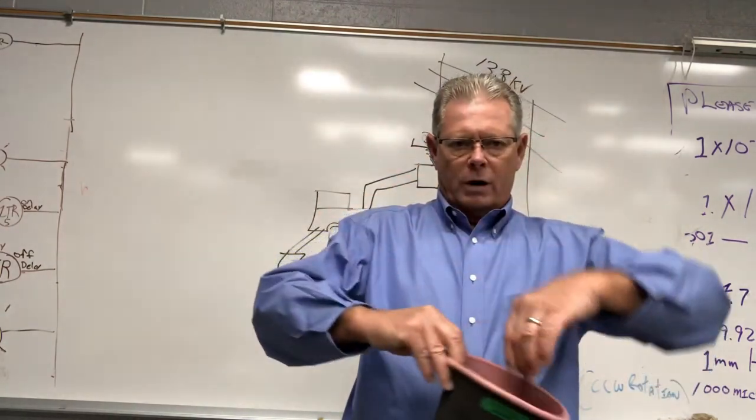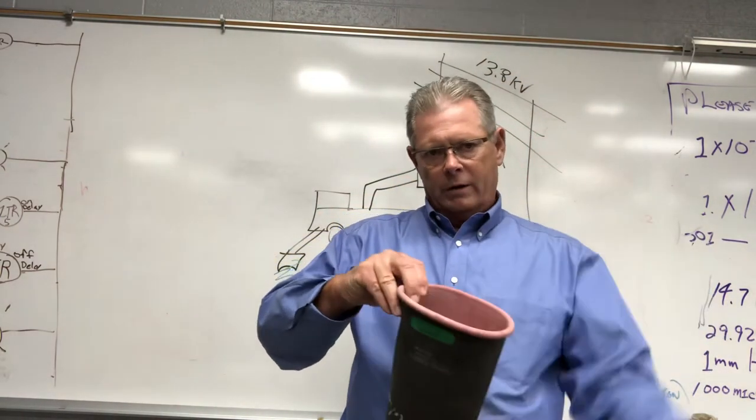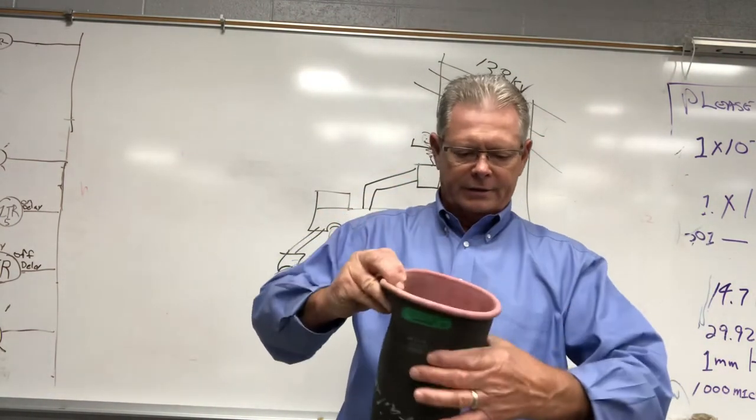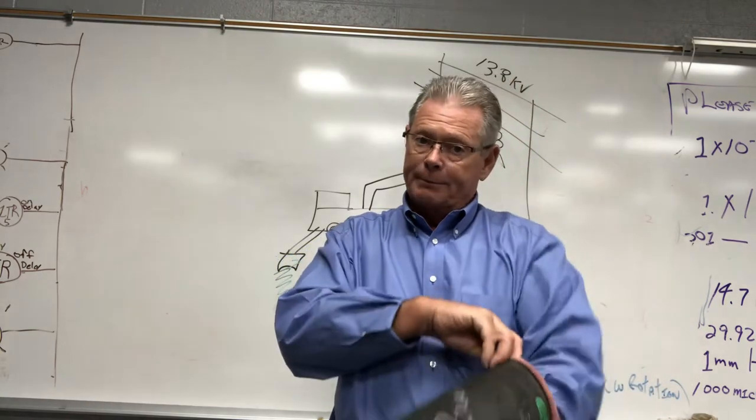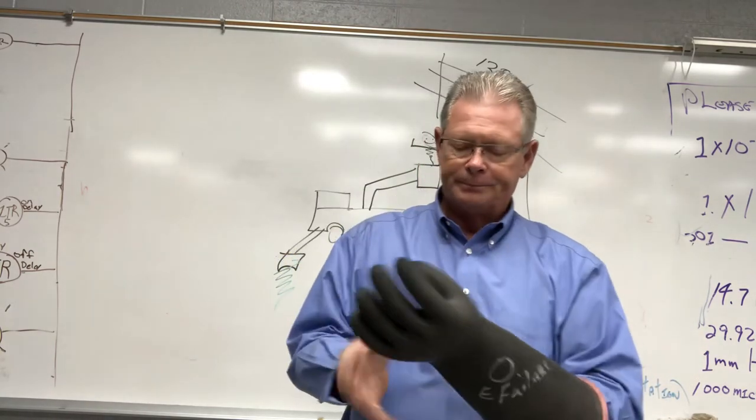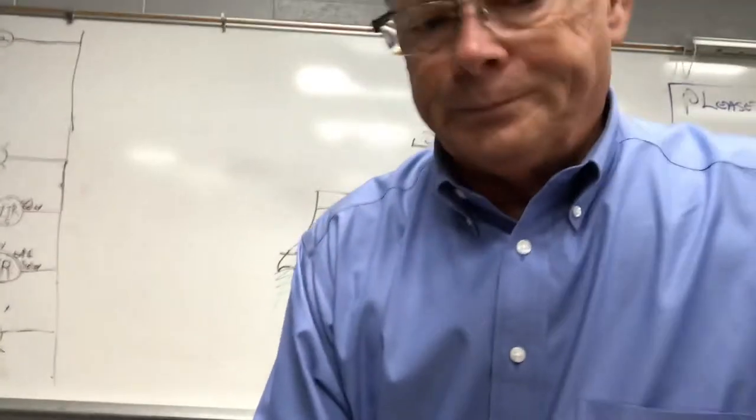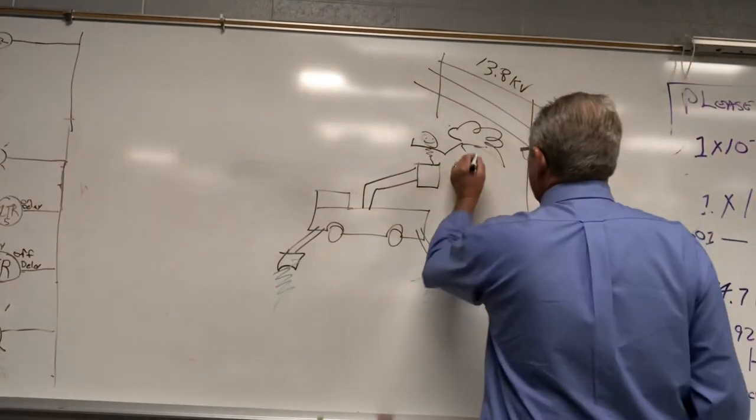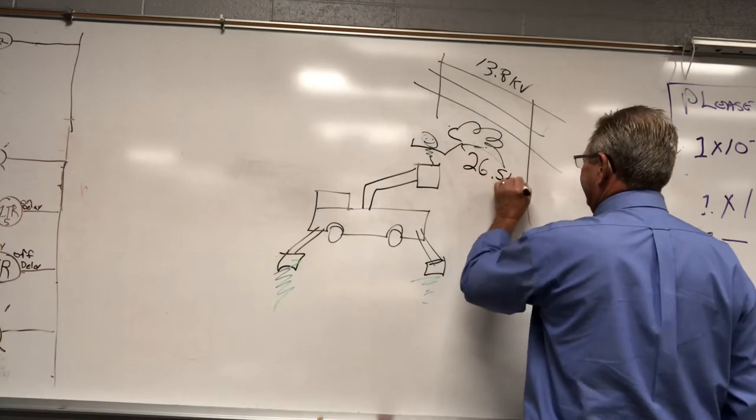They put them in a vat of water with an electrode. They fill them with water, put them in a vat of water, take them down so far, and they see if they can pass a current through the rubber. So these gloves are 26.5 kV.